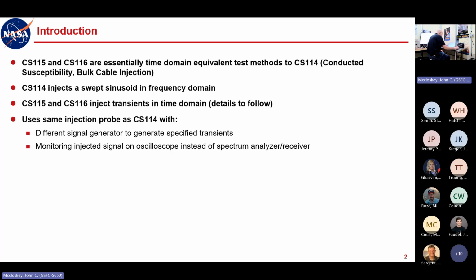It uses the same injection probe as CS114 with just a couple of differences. It uses a different signal generator to generate the specified transients, and those are the boxes on the table here that I'll show you when we get to that part. You monitor the injected signal on an oscilloscope instead of a spectrum analyzer or receiver, which stands to reason if you're dealing with a time domain event, a time domain transient, you want to look at it on an oscilloscope.